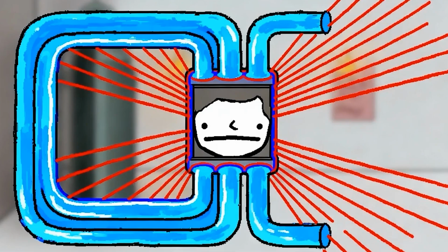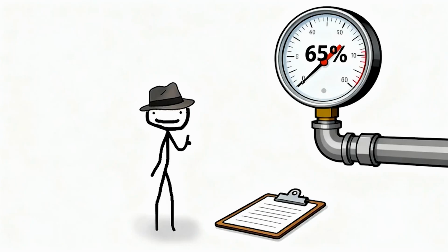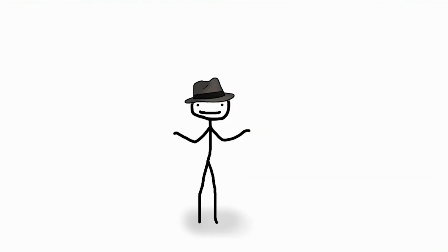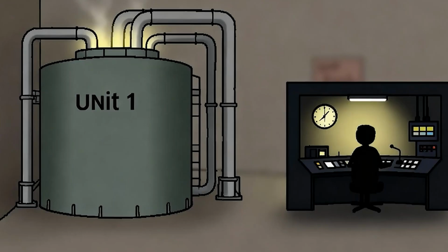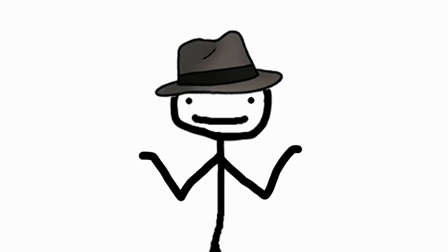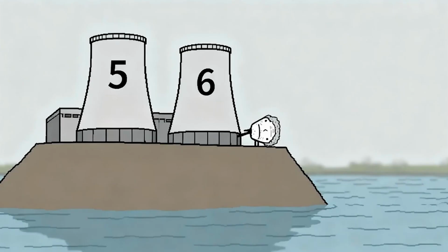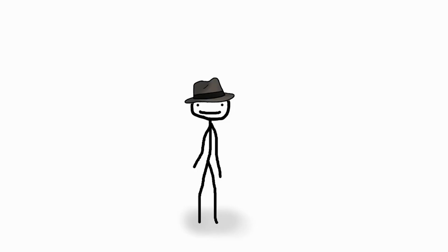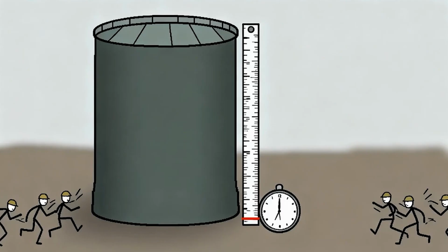Here's the thing, the isolation condenser's secondary loop, the cold water side that actually absorbed the heat, was still at 65% capacity when engineers inspected it later. If the valves had stayed open, if DC power hadn't failed, if operators had understood the system's state in the dark, Unit 1 might have stayed cool long enough for other measures to kick in. Units 5 and 6, farther from the flooding, had one surviving air-cooled generator and avoided meltdown entirely.